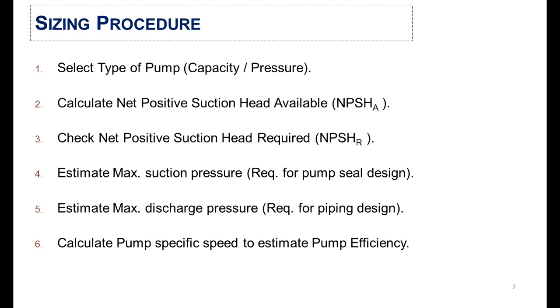After collecting the required input data, you will start the sizing procedure. The first step is to select the right type of pump as per your required capacity and discharge pressure. In the second step, you will calculate the net positive suction head available (NPSHa).